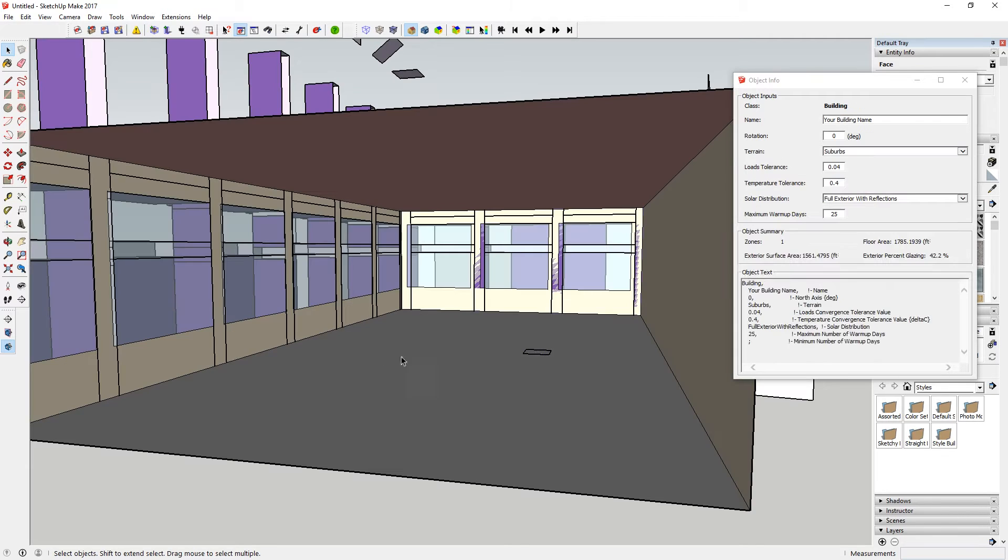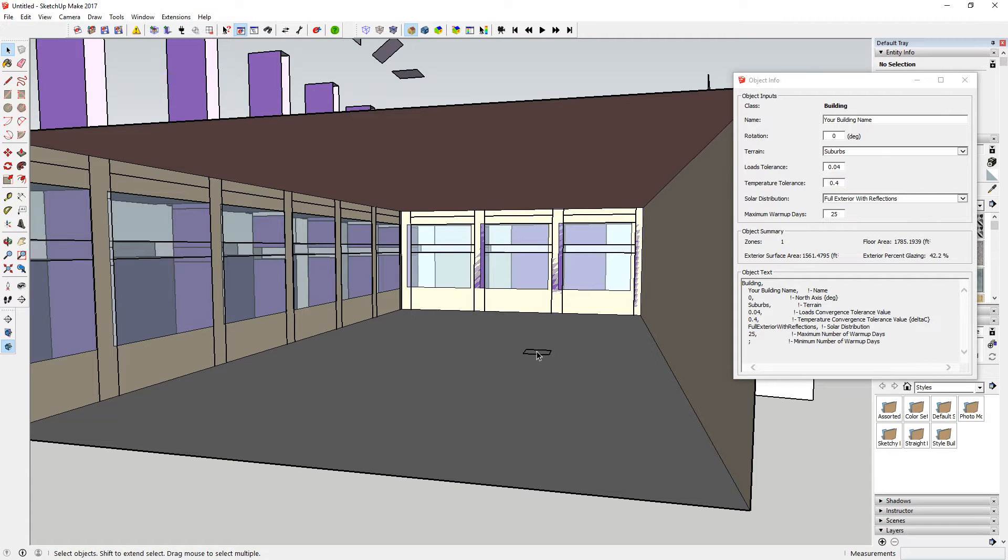Now the trick here is that you want the daylight sensor to be towards the darkest part of the zone that is being dimmed.